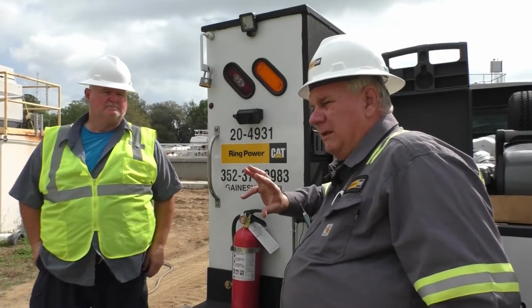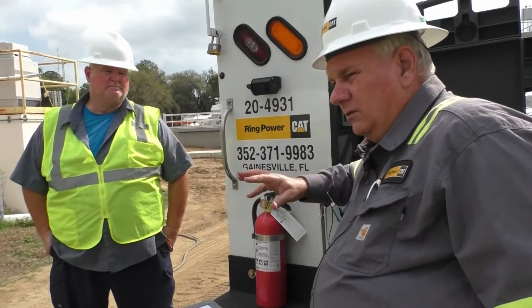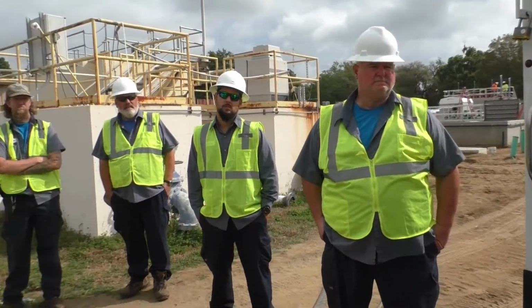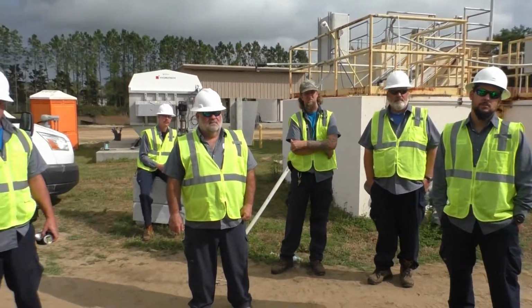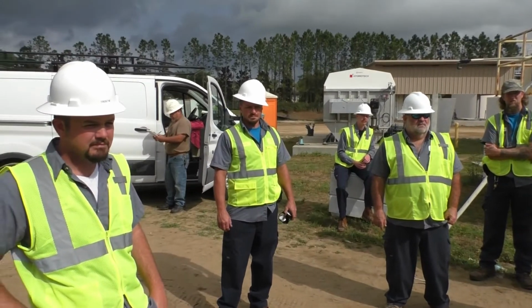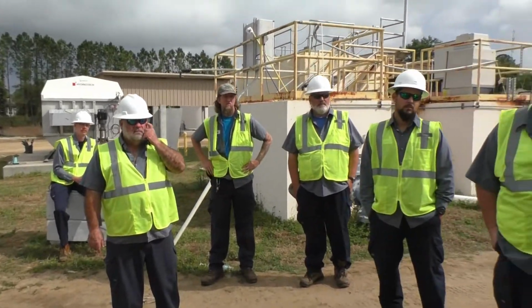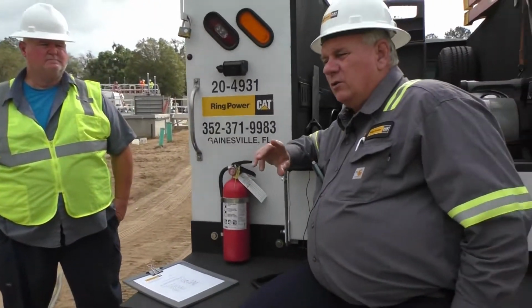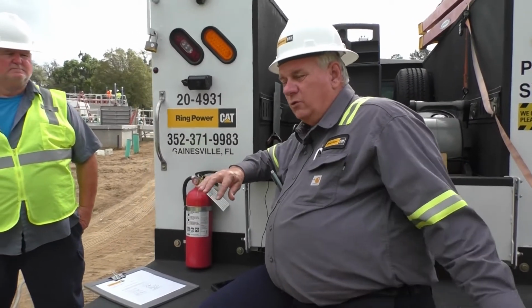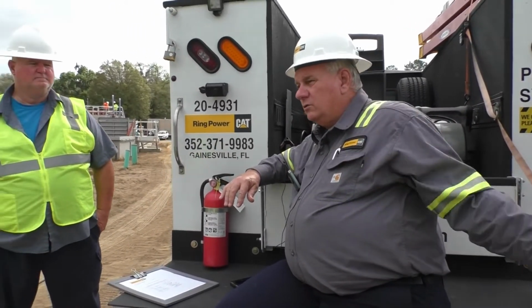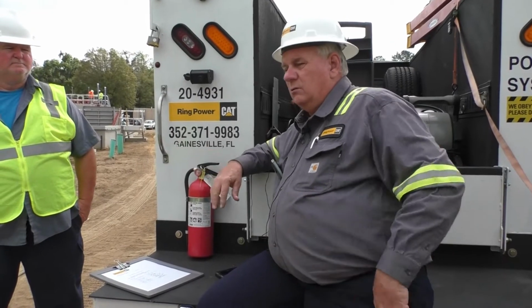Pretty much the same. You'll see them on a lot of the generators of the last 5 years or so and beyond. This is an 800 kW unit, 480 volt. It has 2 transfer switches. We have a single breaker on the generator that feeds both switches. So if you trip the breaker on the generator, you will lose both transfer switches, just so you know.